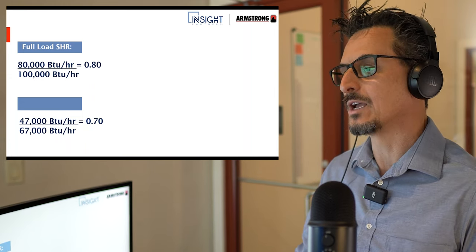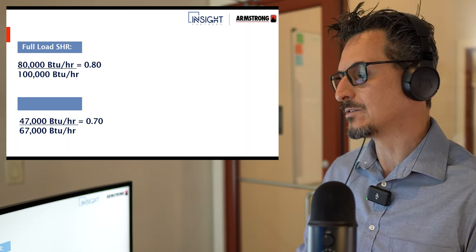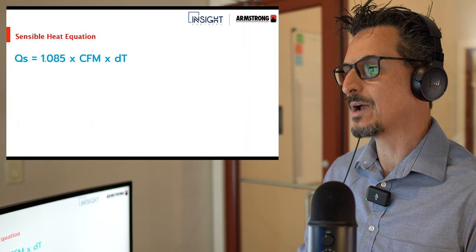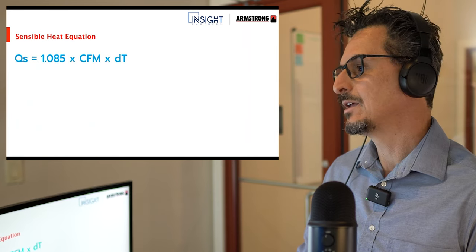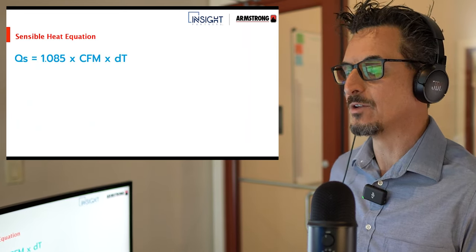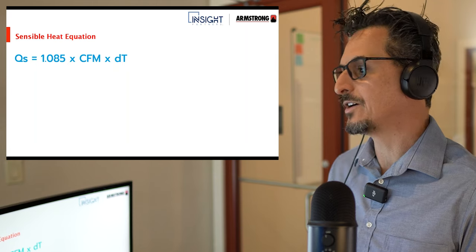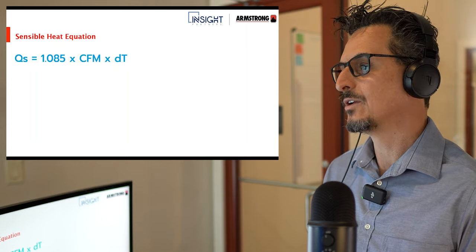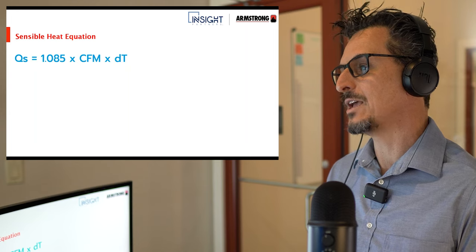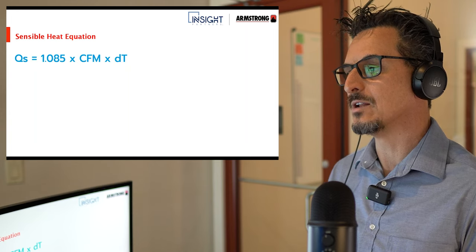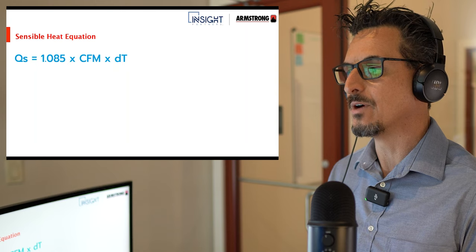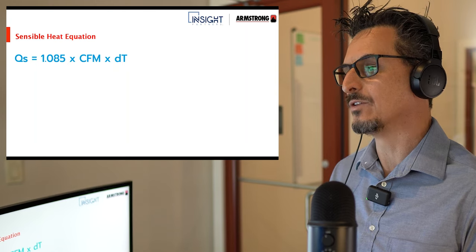The part load is 47,000 over 67,000, which represents a 0.7 part load condition — pretty reasonable. We're going to look at a reduction in sensible heat and see what happens. If you are new, this is the sensible heat equation — very important. It's one we use all the time throughout our careers, whether you're calculating sensible heat of a space, a coil, an electric heater, et cetera.